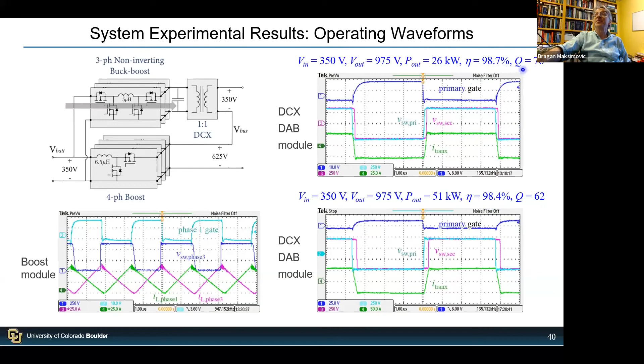Here are waveforms associated with the DCX, a dual active bridge type structure, zero voltage switching everywhere, very clean waveforms. This is at 50 kilowatts going through the DCX with 98.4% efficiency and a Q of 62. Here's half power, 26 kilowatts, with 98.7% efficiency and a Q of 76.